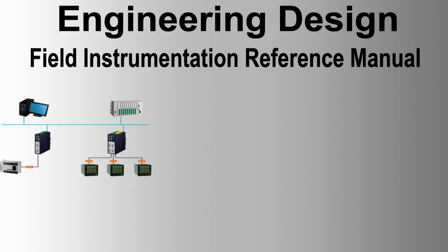Specific instrument requirements. Instruments should use SI units unless otherwise specified. Instruments must have defined ranges and spans, ensuring they cover the operating window with appropriate accuracy. Signal transmission can be electric or pneumatic, with specific protocols recommended. Power supply should be determined based on the criticality of the application, with options for uninterruptible power supply.